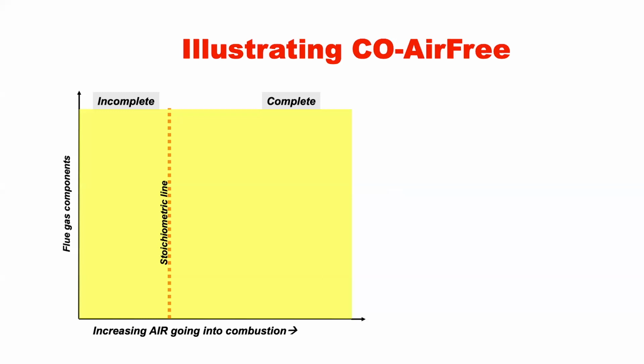Let me throw up another illustration here, going back to the stoichiometric line, but we'll look at it more simply with oxygen and CO level. As the oxygen level increases, the CO level decreases, not because less CO is being made, but because CO is being diluted by increasing concentrations of air, which the oxygen is telling us about. If we could remove that factor of oxygen, the CO air-free would look like the same number, like taking it back to the stoichiometric line for the whole range of testing for excess air. So I'll do that one more time. Here you see a declining amount of CO. Here you see a consistent amount of CO air-free because of the calculation of CO air-free.